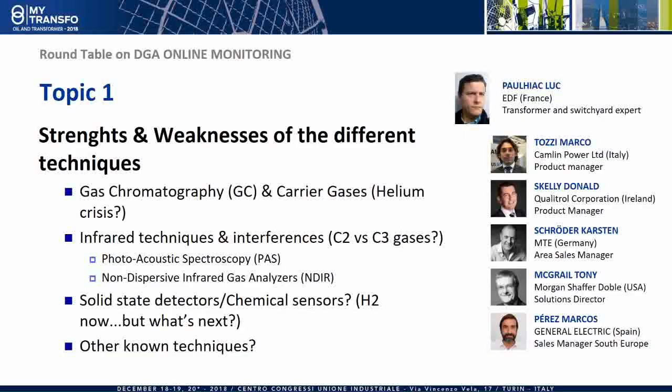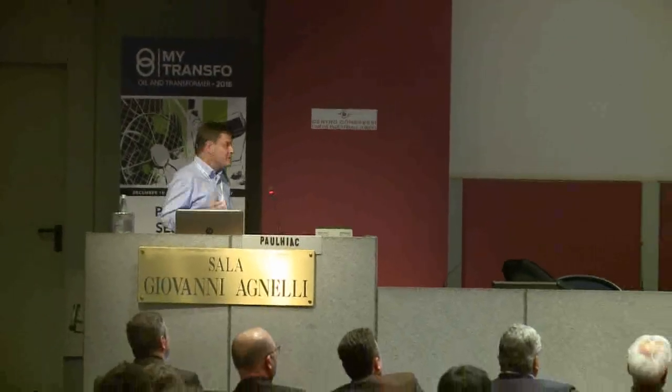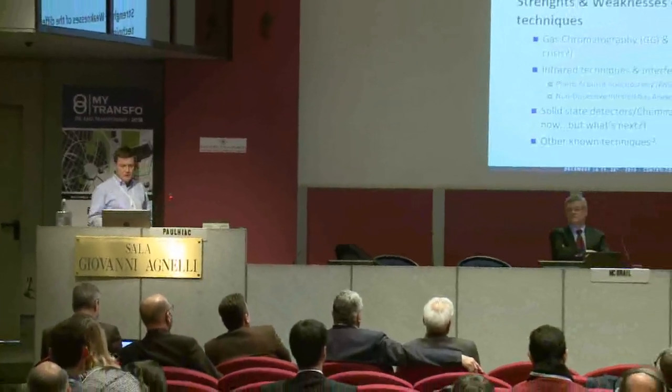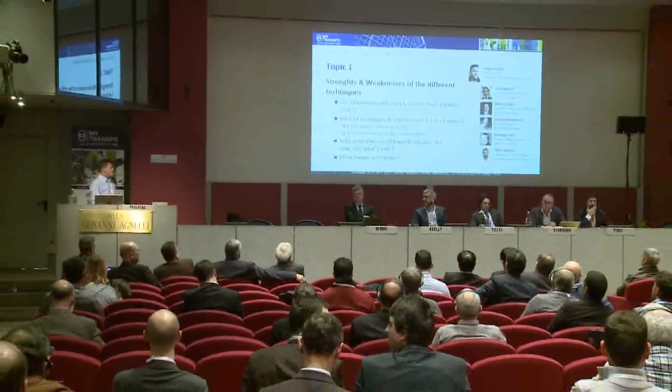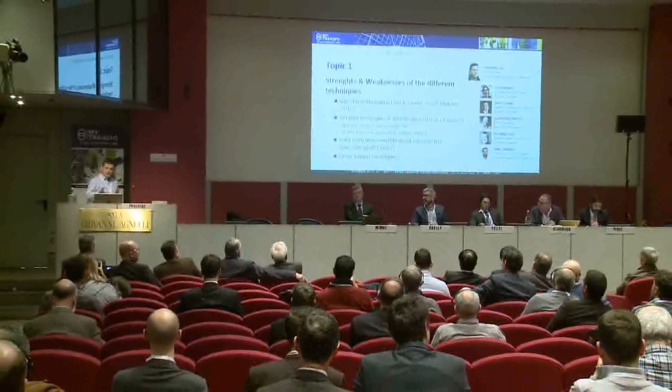I read all your answers to the questions, and I really want you to stay on the technical side, if possible, not on the commercial side. So the topic one is strengths and weaknesses of the different techniques. Mainly we have two techniques: the classical one, gas chromatography, and the infrared techniques that can be divided into photoacoustics and non-dispersive infrared gas analyzers. We also see some solid state detectors and maybe there are other known techniques. Can each of you explain what are the pros and cons of the different techniques and also the issues that they will have to address?